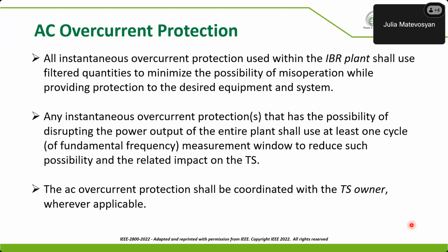So fairly simple. A little more detail: instantaneous overcurrent protection used within the plant shall use filtered quantities. Same reasoning as I mentioned when we were talking about overvoltage protection. It allows some transients to get filtered out and allows the protection to become more reliable. Any instantaneous overcurrent protection that has the possibility of disrupting the output of the entire plant, so anything applied at the POM, for example, or on a collector bus, where a misoperation means the entire plant could be lost, shall use at least one cycle measurement window to reduce any misoperation from transients and the like. The AC overcurrent protection obviously needs to be coordinated with any similar protection that is used by the transmission owner on the transmission system.